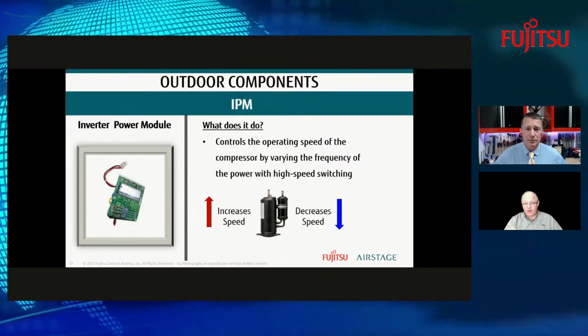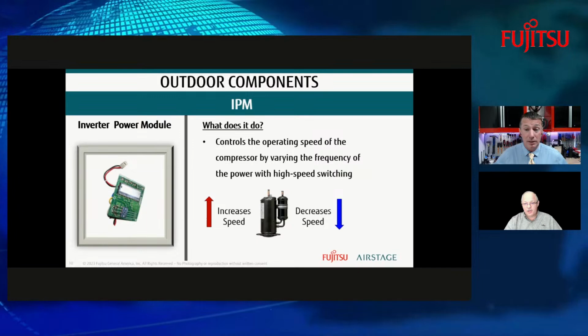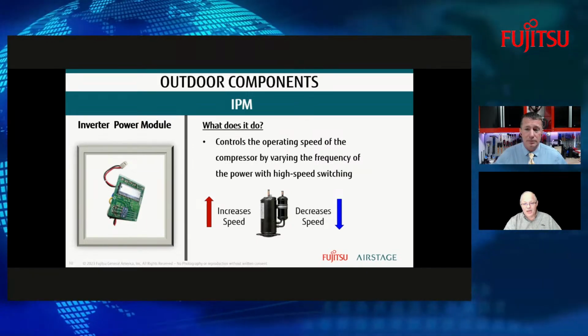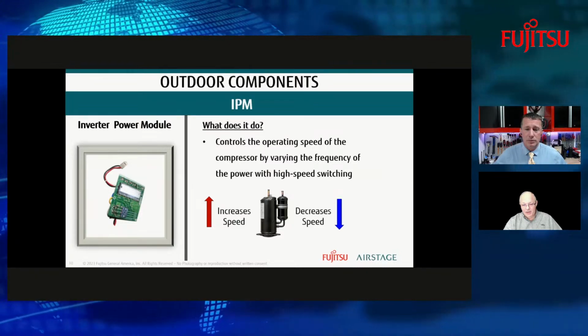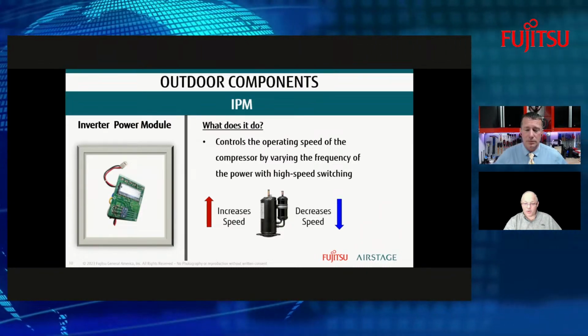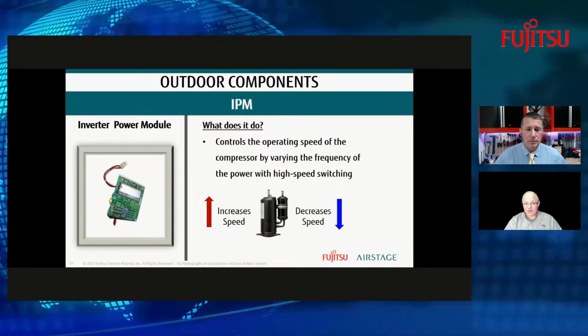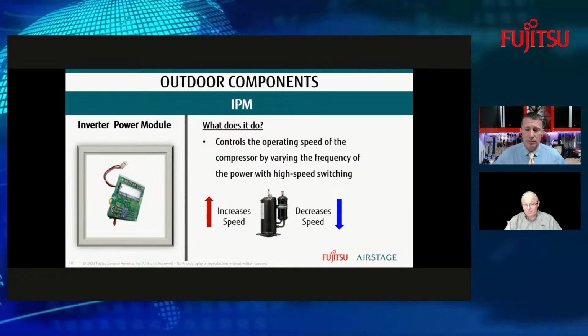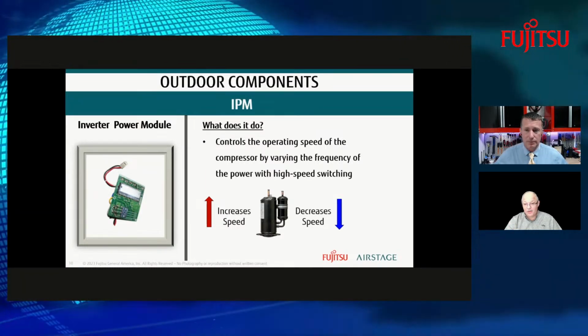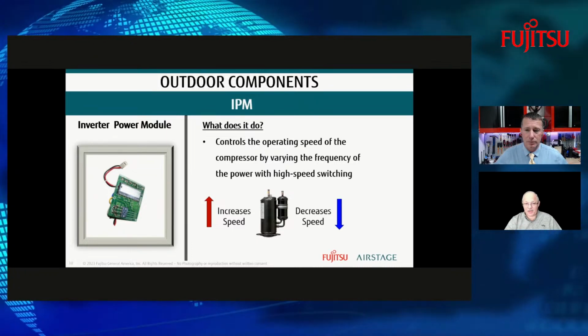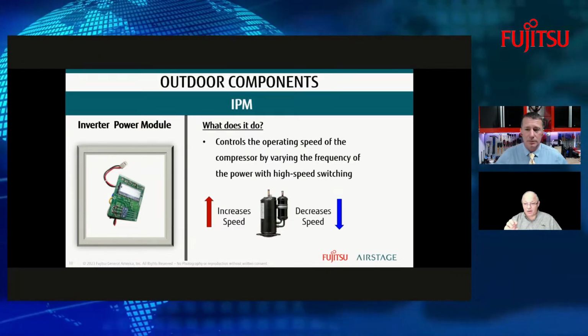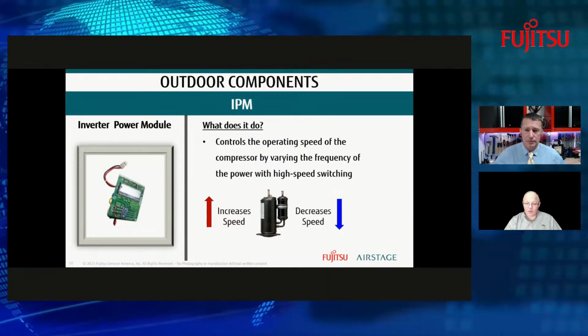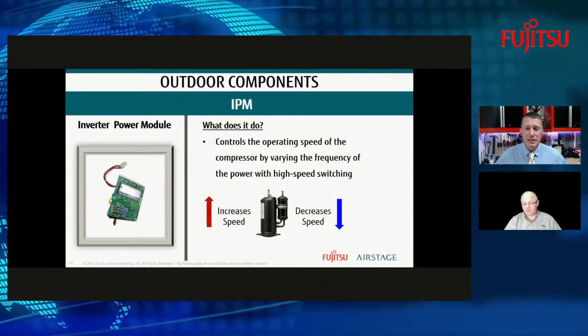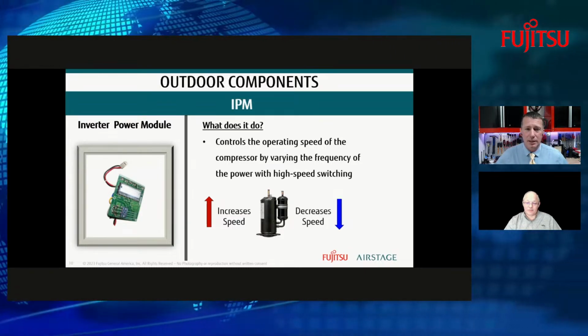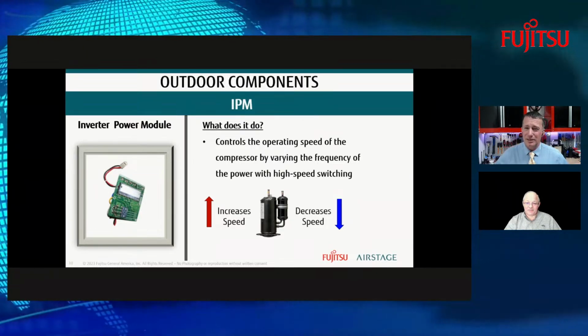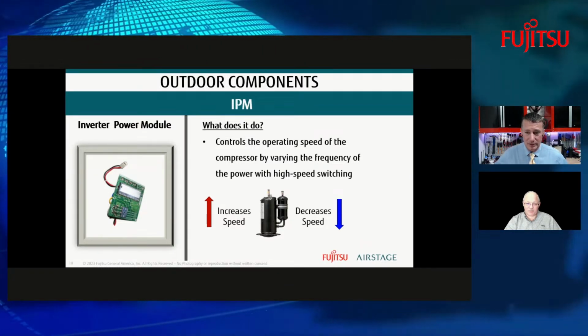Okay. And this is what controls the operating speed of the compressor, changing and varying the frequency of the power through high-speed switching. So it can speed it up and slow it back down depending upon what's going on with the system at the time. It too has a little diode on it that gets very hot. It has to be heat sink pasted down as well. But this is the little brains of running that compressor and telling it at what speed it's supposed to run at a given time. I've also seen in some of my installation manuals the IGBT, insulated gate bipolar transistor. Is this the same design, same function? Yes. Okay.